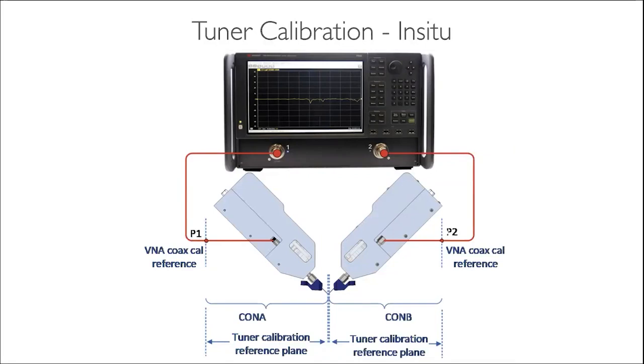And then, because let's say the low frequency tuners are a bit bulkier, some people might just say, no, I just want to calibrate there, but I'm going to add a cable from the tuner to the probe tip, and if I want to swap out the cable from time to time, I can do that, and I don't affect tuner calibration. But at high frequency, you can't really do that. So what we do is we have an in situ calibration.